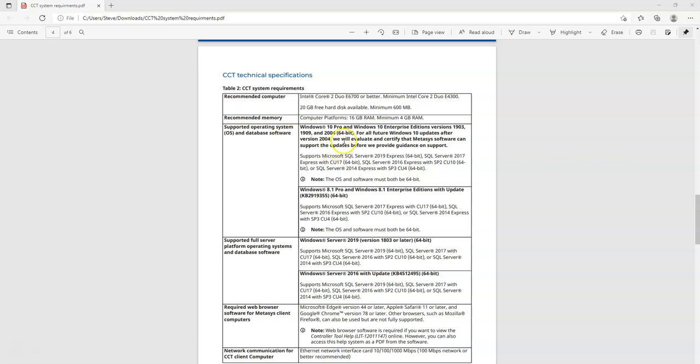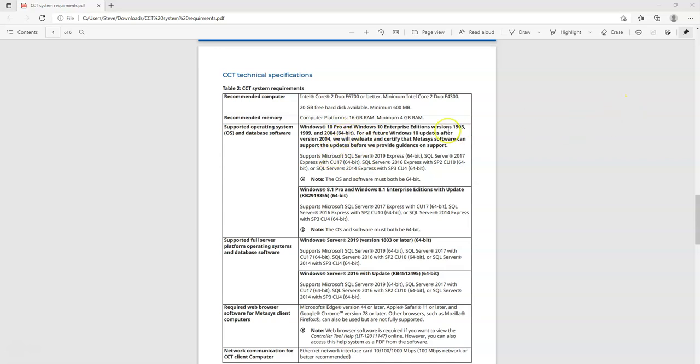I just want to go through that because not everybody has this. It does require Windows 10 Pro or Enterprise Edition. Must be 64 bits. That's because all this SQL that has to run in the background that CCT relies on. It will not work with Windows 10 home. So if you go to Best Buy and get your computer and it's got Windows 10 home on it, you're gonna have to upgrade it to Windows 10 Pro or Windows 10 Enterprise.